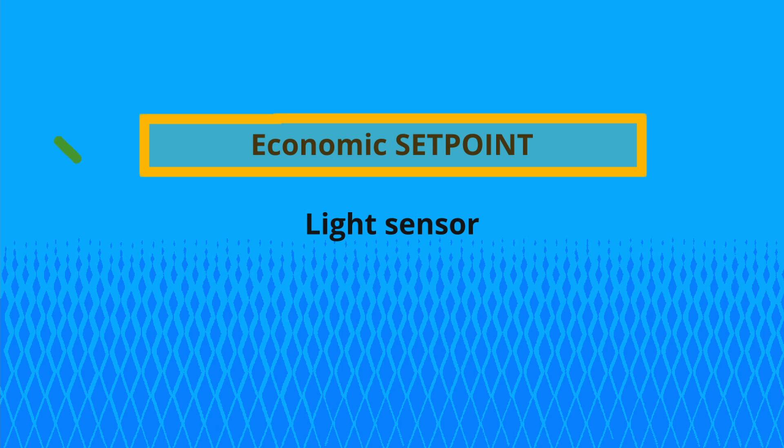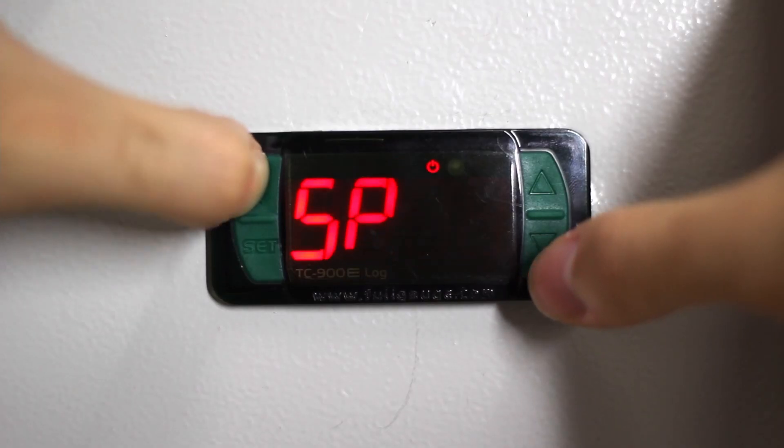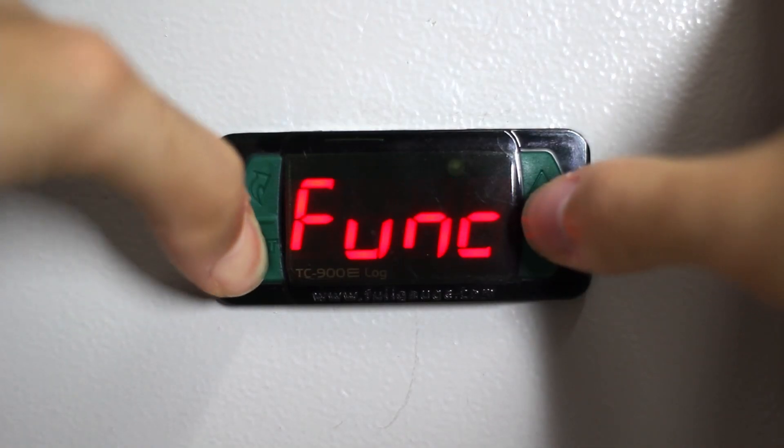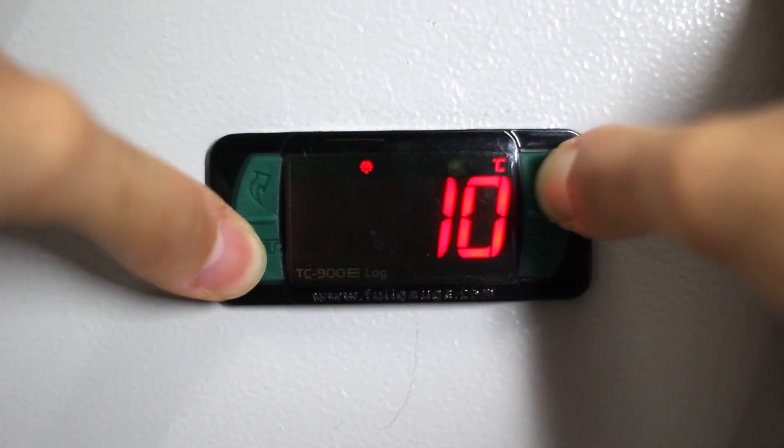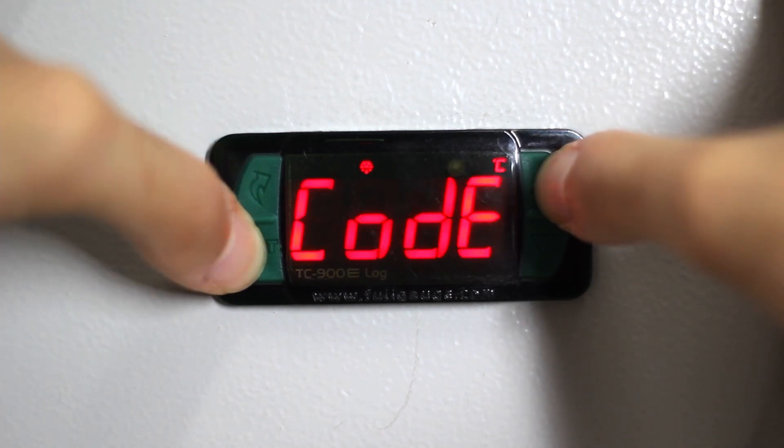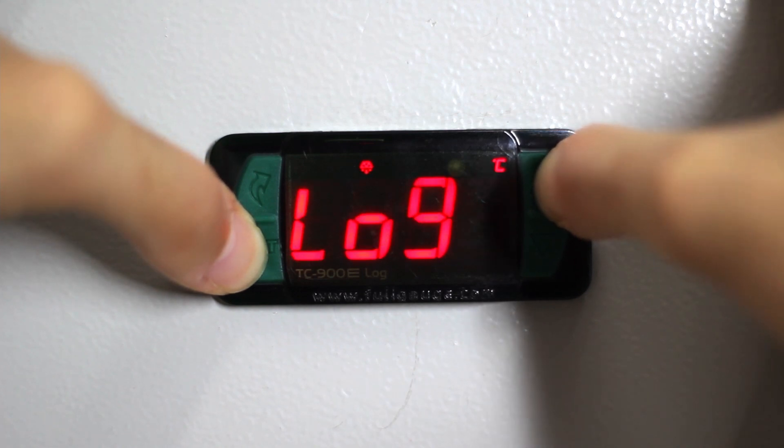Having economy set point activated, we must enable the light sensor. Pressing the top left key, find FUNC option and enter again the access code 123. Use up or down arrows and find the Lumi feature display, then press SET.